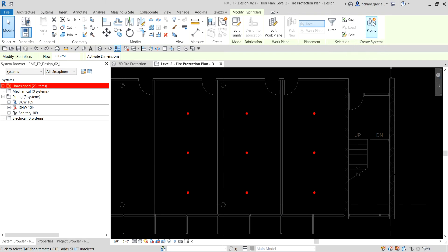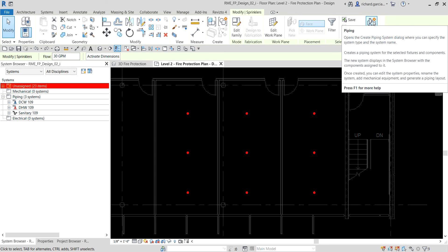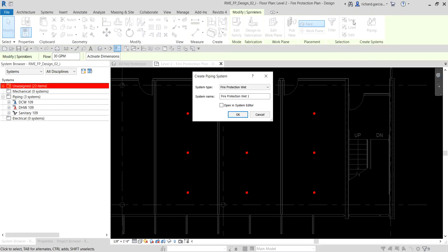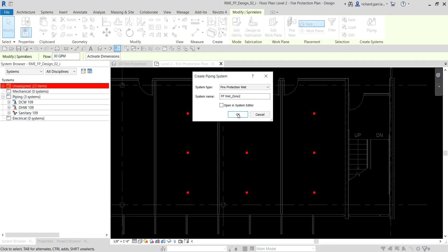After selecting the sprinklers, from Create Systems there is the Piping tool. It opens the Create Piping System dialogue where you can specify the system type and system name. I'm going to name this one 'fp_wet_zone_2'. The system type here is only Wet because the connector on these sprinklers is a wet sprinkler connector, so the system type is Fire Protection Wet. I'll select OK.